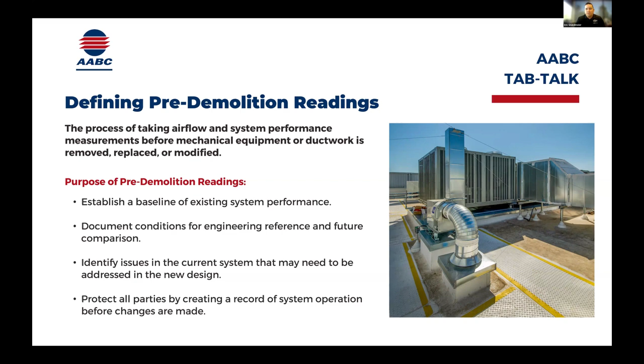One of our last points is it protects all parties. That's the other great thing about having the data before we made any modifications—we can go back and look at that data and analyze what happened to the system. It's protecting us because, for example, if an engineer designed a project for 10,000 CFM, but we measured the existing equipment and it only could achieve 6,000 CFM, we already know the project needs to be re-looked at. So these are all the things that help protect all parties involved, and it's very important.